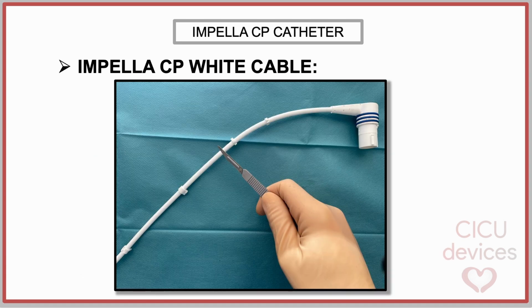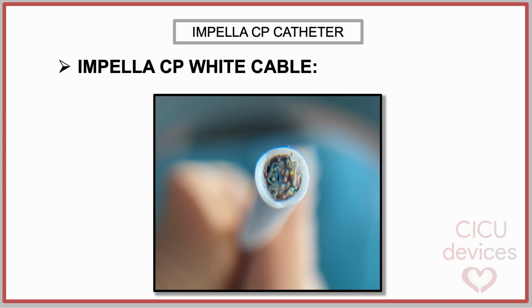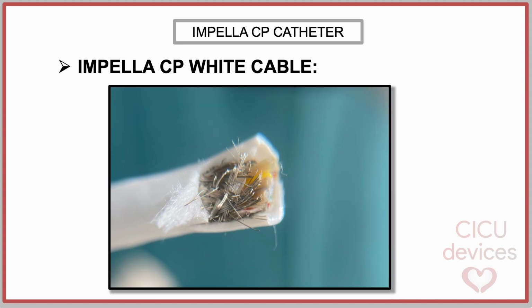If the driveline is transversely cut with a scalpel, the following internal structure is revealed. The outermost layer consists of a medical-grade white silicone jacket, engineered to provide robust mechanical protection as well as resilience against physiological fluids. Beneath this primary insulation, a fine metallic braid mesh encases the cable bundle, serving as both a physical reinforcement and an electromagnetic interference shield, crucial for maintaining signal integrity and device reliability in complex medical environments.